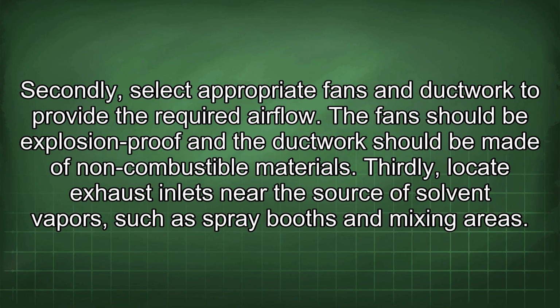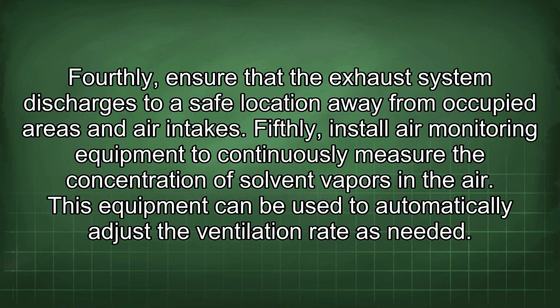Thirdly, locate exhaust inlets near the source of solvent vapors, such as spray booths and mixing areas. Fourthly, ensure that the exhaust system discharges to a safe location away from occupied areas and air intakes. Fifthly, install air monitoring equipment to continuously measure the concentration of solvent vapors in the air. This equipment can be used to automatically adjust the ventilation rate as needed.